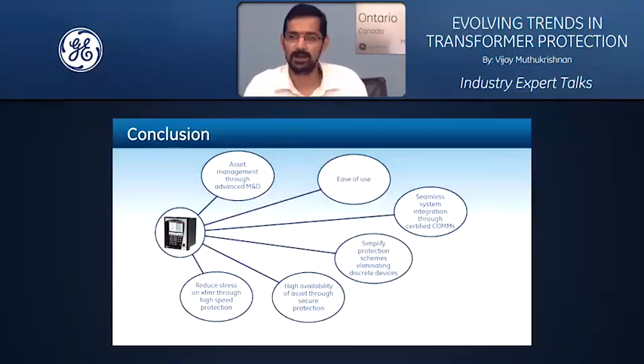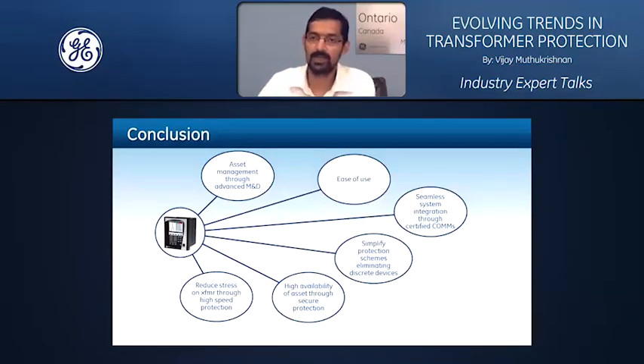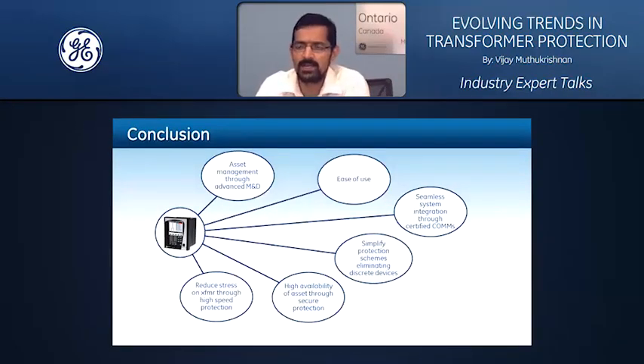So it needs to have advanced functionalities like directional supervision and CT saturation detection to make your differential stable for true fault conditions. Then your ability to apply to a variety of simple to most complex applications and allow you to eliminate discrete devices and converge all of them into the protection relay so that you can cover a variety of applications. This device should be seamless to integrate into any type of network architecture on any type of protocol built on a layer of security. Asset management capabilities let you extend the life of the transformer, making it very easy to use.